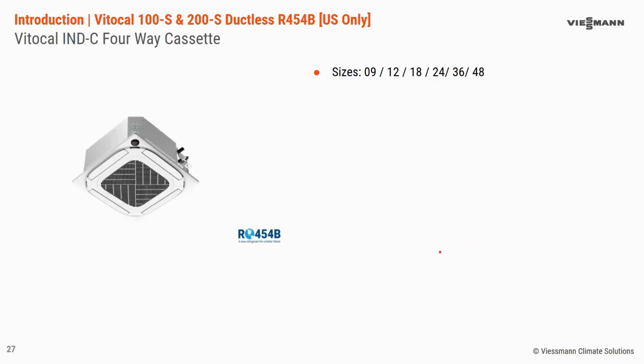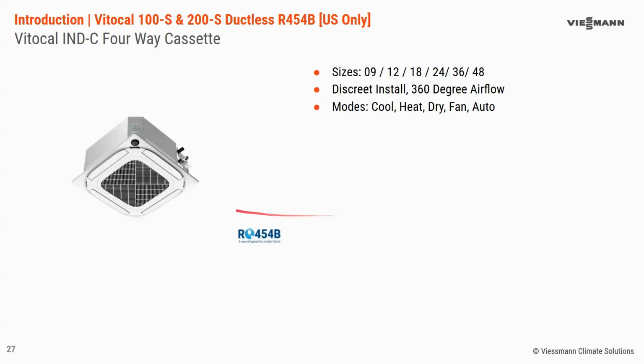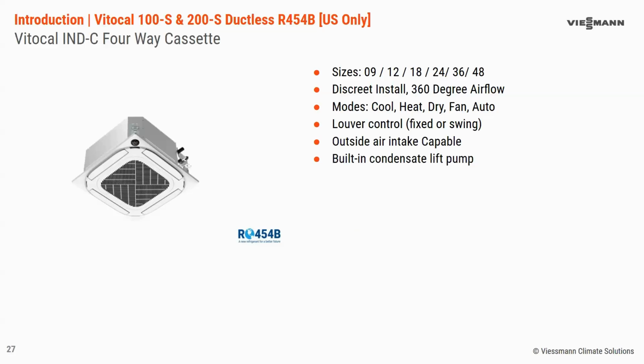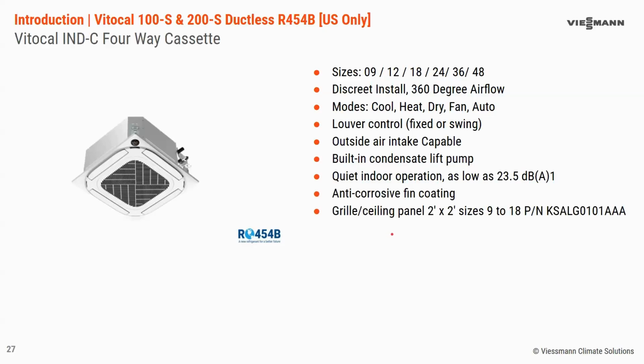On the 4-way cassette, we've got 9 to 48,000 BTU, with the 36 and 48 being the light commercial. The 4-way cassette allows for 360-degree airflow in a discreet installation up within the ceiling, so that grill panel is flush with the ceiling essentially. Same modes as we're going to see on all these indoor units. You have louver control. There is the potential for outdoor air intake with this unit. There's a knockout for that. Built-in condensate lift pump. Again, quiet indoor operation, same features of the coated coil.